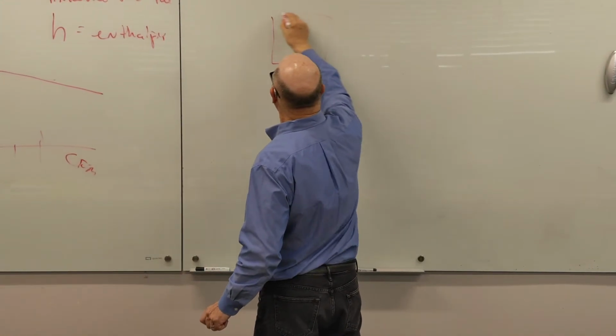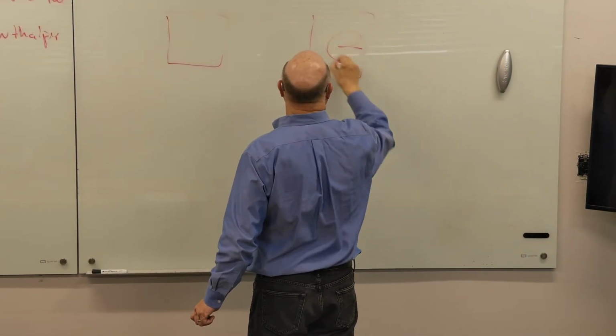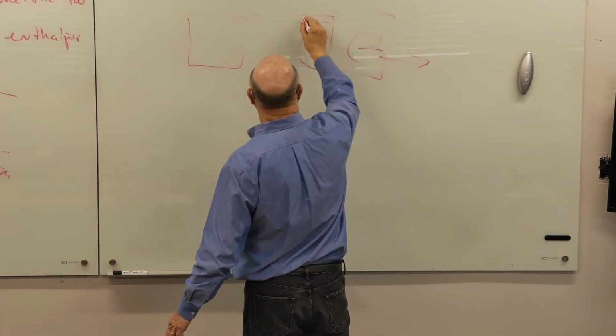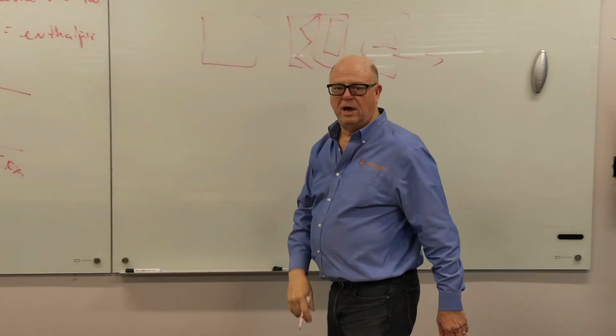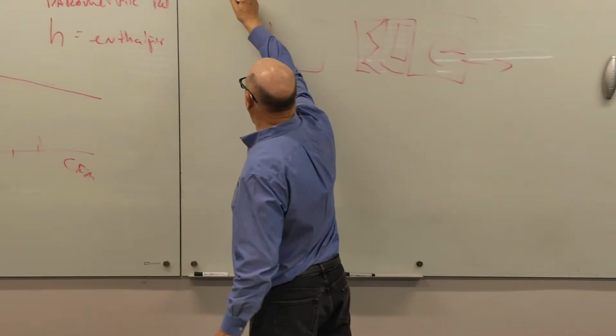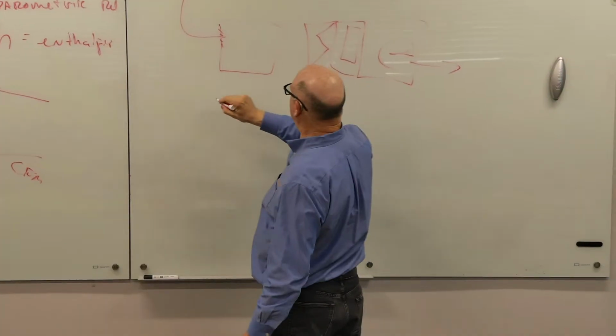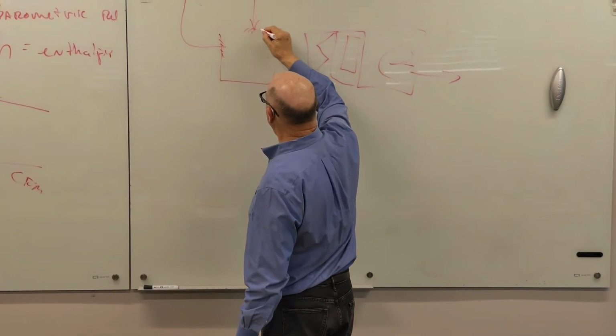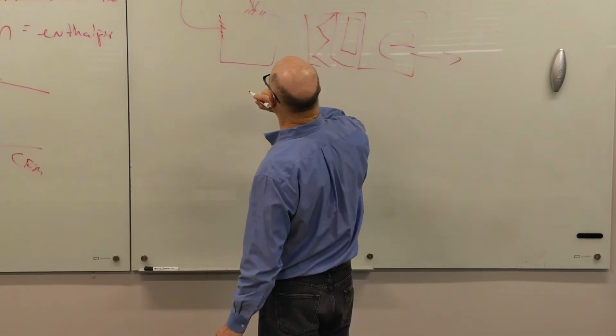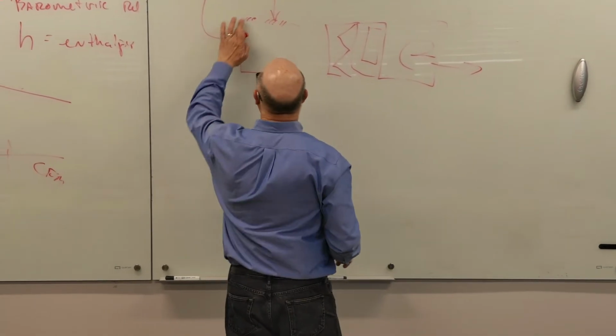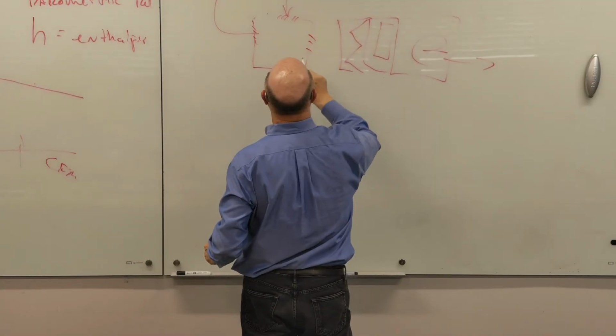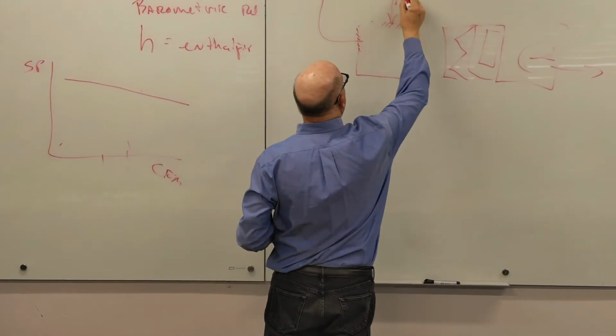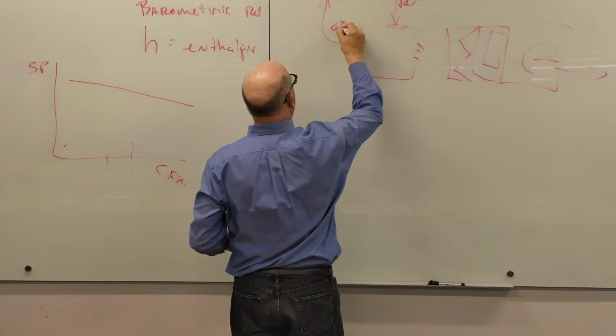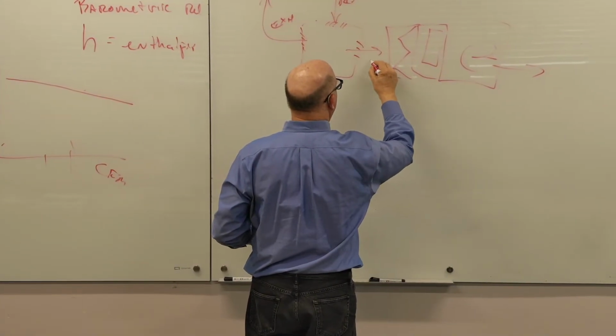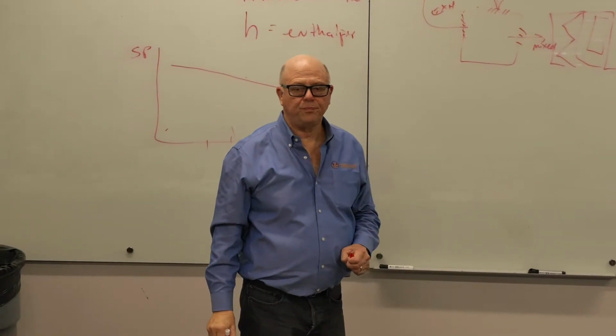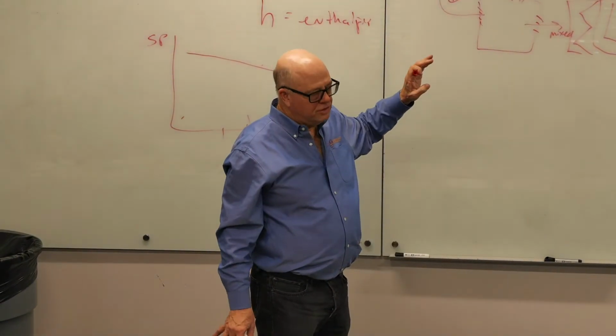So I'm going to draw this as though it was an air handling unit. Here's my air handler fan, and the duct comes out. And I've got a cooling coil. And I've got a filter. And then I've got my economizer section. My economizer section has outside air that comes in through some dampers. And it's got some return air that comes in through some dampers. And it's got relief air. That's not the traditional setup. Here, let's do it this way. Here's return air. Here's exhaust. And this is your mixed air. This is simplified.